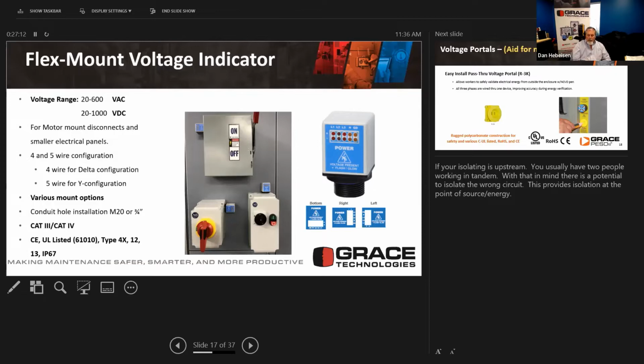So it offers some flexibility there to get out on the plant floor where you're seeing more and more of the mechanical lockout tagout and some enhanced electrical, and the opportunity to verify quickly and easily that the system has cleared. On these, for example, it could be on a long conveyor system or something like that. There is a mechanical jam on the equipment, so you're starting to get a buildup of boxes or something like that. You could simply walk up, see the disconnect, throw the disconnect, watch the stored energy go away, then go out, because now there is no energy flowing, and you're going to remove that stuck box and then come back after you've cleared that, go ahead and throw the disconnect and then bring that particular system or conveyor up and running. So it's very quick, very efficient, and becoming very popular.